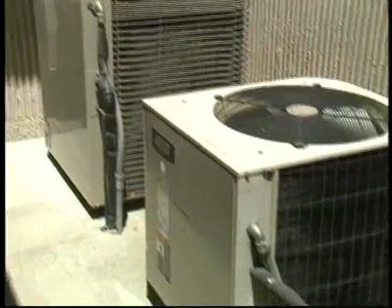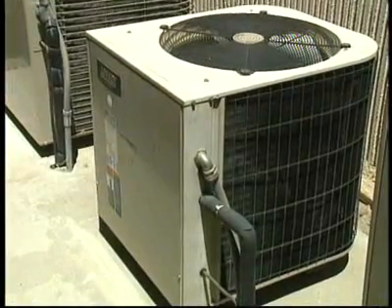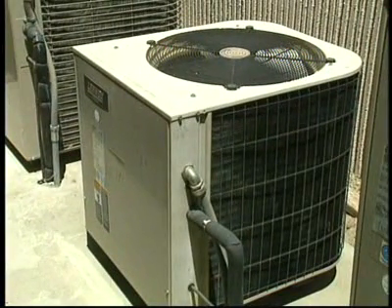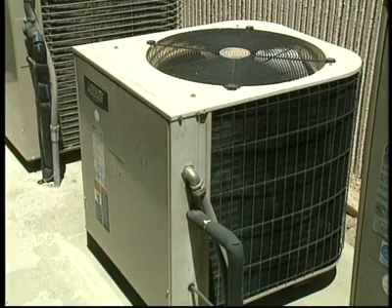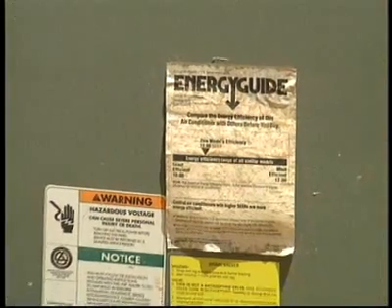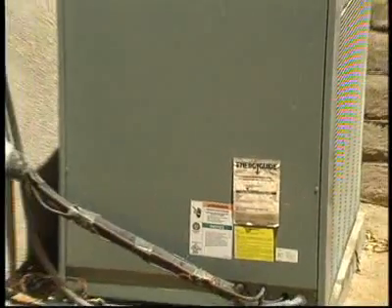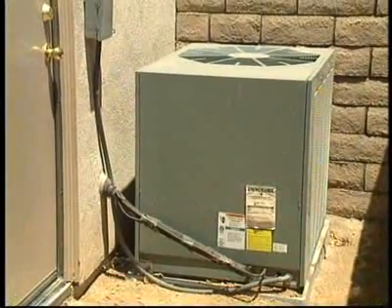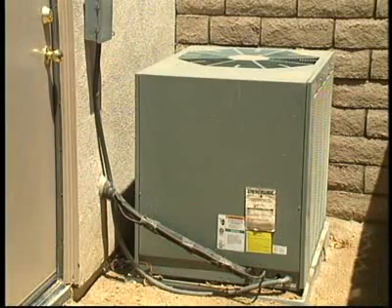Yeah, it turns out unlike large cars where for most consumers bigger is better, the average consumer is going to be better served by having a smaller sized air conditioner. And the reason has to do with their operation. When you have an air conditioner that's oversized, it cycles. It turns on, it turns off, it turns on for a couple minutes, turns off. Whereas a smaller size air conditioner runs more consistently across the hour. And it turns out it's more efficient when it runs for larger run times.